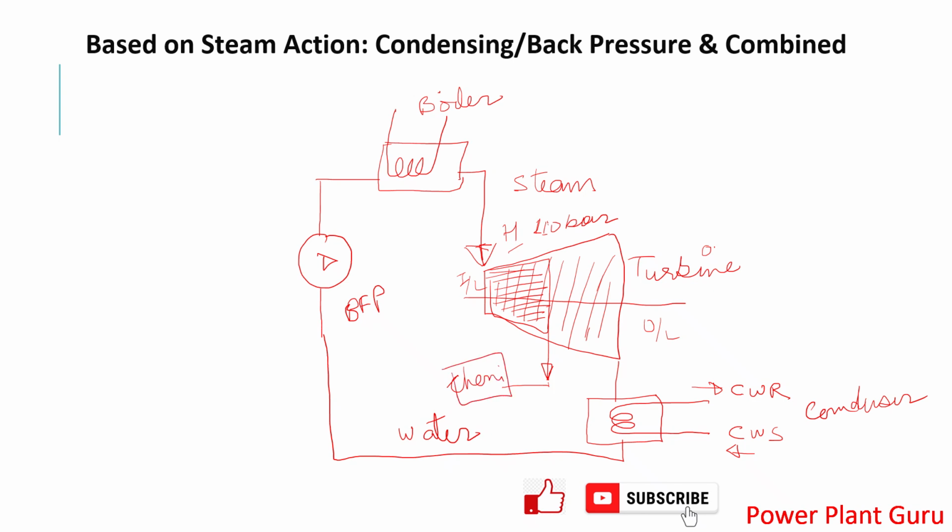Here you are using steam for heating, and then the steam condenses, and you can put it back to the boiler feed pump or condensate cycle. So you are utilizing the steam for generating power, and after the power is extracted, you still have certain pressure and temperature, and you will have the chemical process requirement where you can match the pressure and temperature you require.